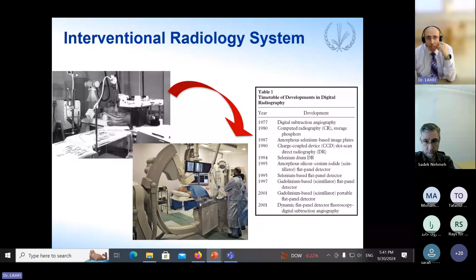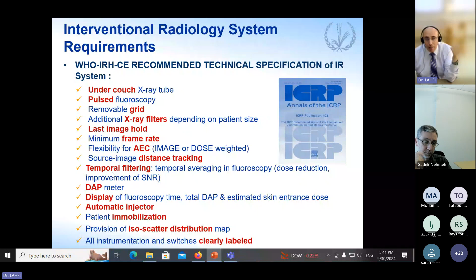The WHO recommended technical specifications of interventional radiology systems, which we should have all of these recommendations. Nowadays, most of our interventional radiology systems have most of them. So we have last image hold, the flexibility of automatic exposure control, temporal filtering, DAP meters, an automatic injector, and so on. Some additional recommendations are road mapping, which uses a reference image on which the current image is overlaid.